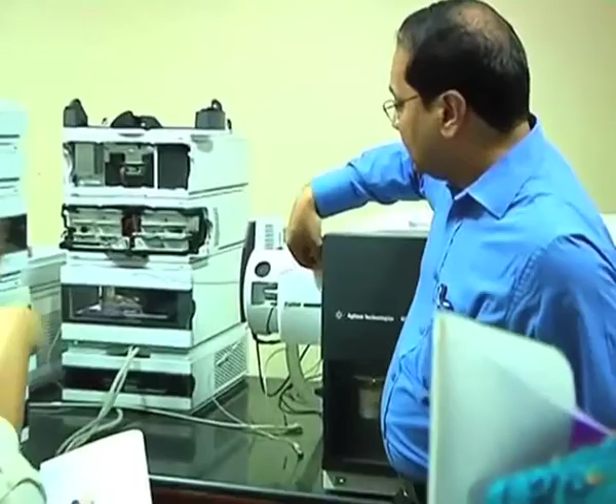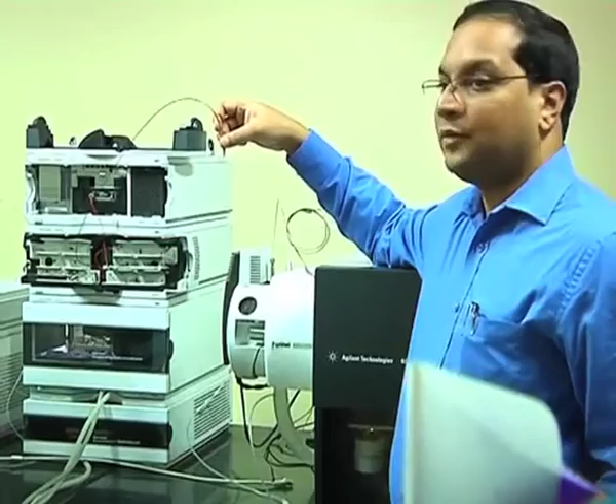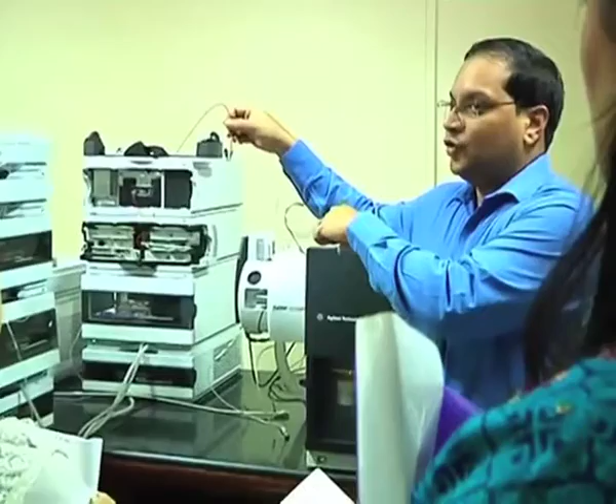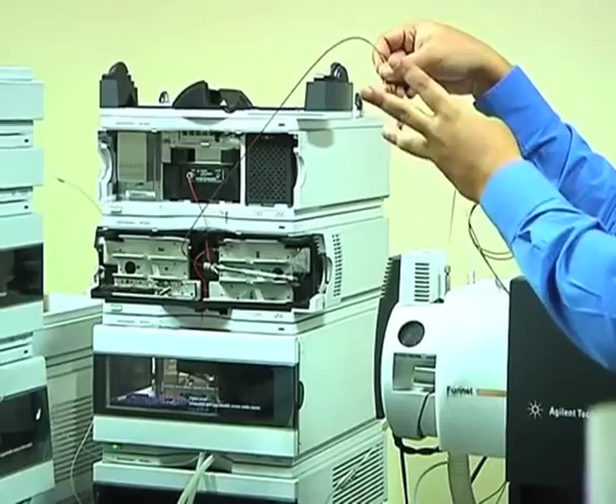Within that peak. So as I told you, it runs through the column and then it elutes in the form of liquid like this. It is coming like this. So right now the method is running at 0.4 ml per minute. The flow rate is 0.4 ml per minute. What is the maximum? You can go to 1 ml per minute. But of course, with this source only, I am not going into details of the specification of the source. This source particularly, but with other sources, MS in general, you may not be able to go beyond 0.5. So right now, initially, when I have to load sample, there is a flow going on which is 3% organic and 97% aqueous. So more of water right now because I have to inject the sample.